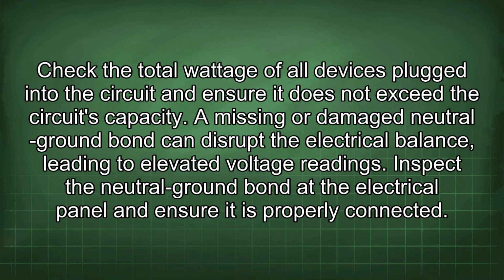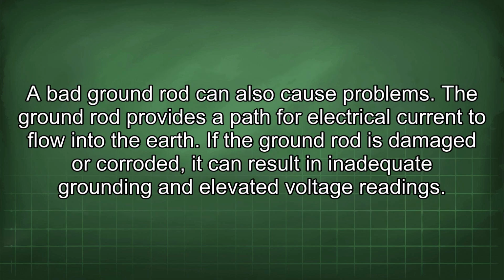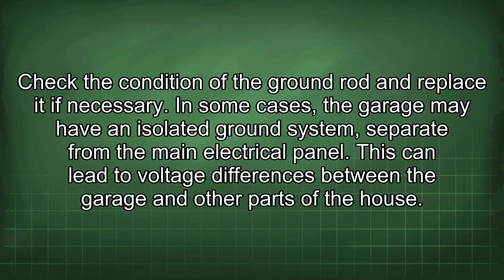A missing or damaged neutral ground bond can disrupt the electrical balance, leading to elevated voltage readings. Inspect the neutral ground bond at the electrical panel and ensure it is properly connected. A bad ground rod can also cause problems. The ground rod provides a path for electrical current to flow into the earth. If the ground rod is damaged or corroded, it can result in inadequate grounding and elevated voltage readings. Check the condition of the ground rod and replace it if necessary.